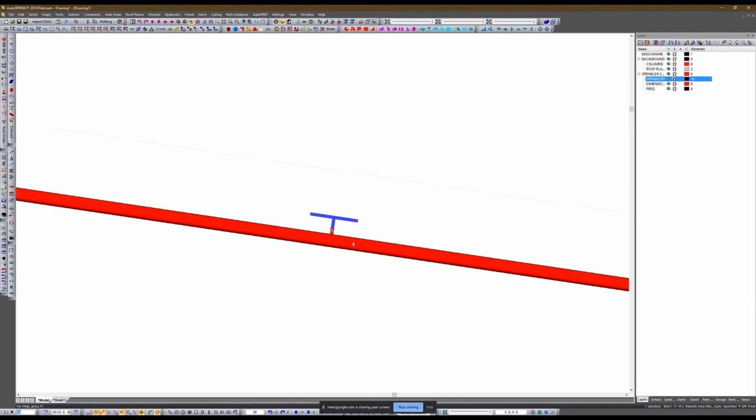This is where things get a little tricky. Most of the time, depending on the scenario that you've got here, as a designer in the past, I haven't bothered too much about this. Now, heads directly on outlets is a little more critical than a head on a sprig, where there's room to play for a fitter that's installing heads on a sprig. They can adjust it up, down. You kind of give them a window, 1 to 12 traditionally, but depending on your construction type, maybe more.